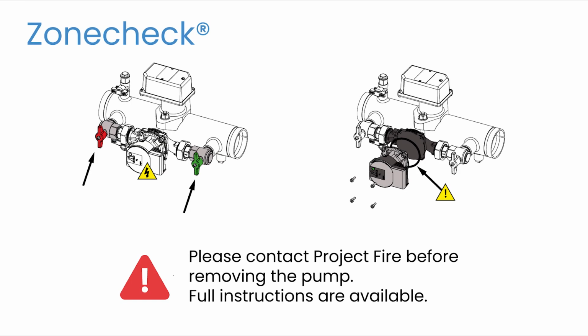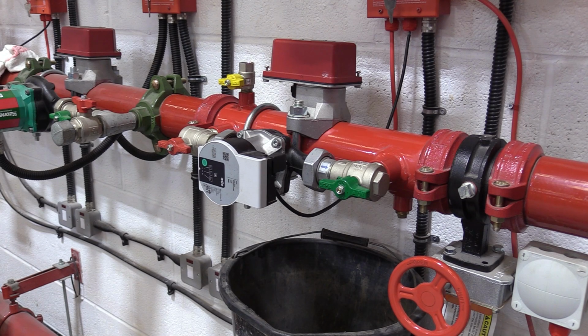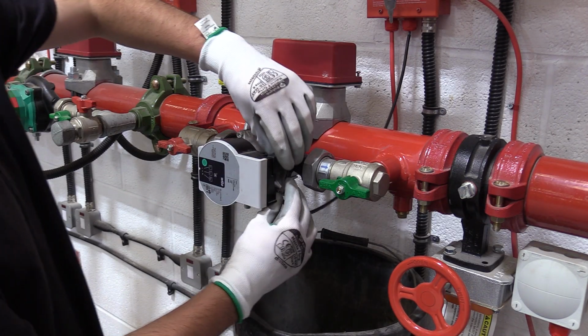If the pump is not running or is not generating sufficient flow despite being thoroughly vented, the pump motor can be removed for inspection and manual operating. Please inform Project Fire before conducting this check, as it involves removing bolts that are tamper sealed. This will not affect the warranty, provided the basic steps and checks have already been completed. Have a bucket and cloth handy, as some water will be trapped in with the pump.